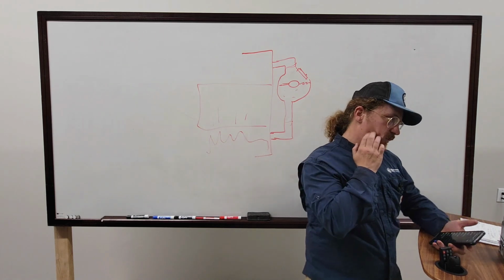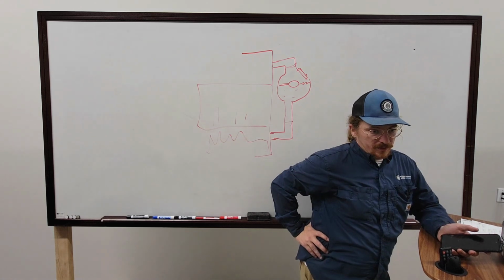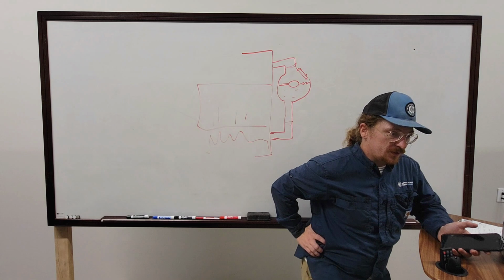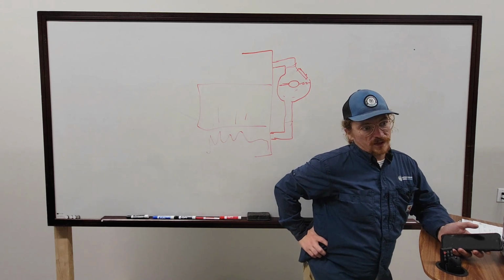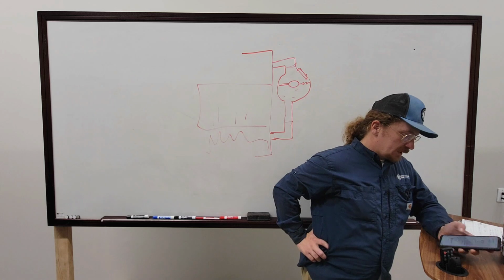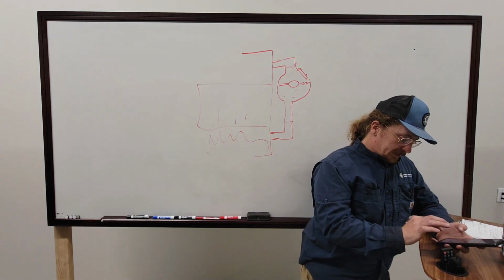Touch on flue gas analysis? No. You want stack temperature below 400, excess oxygen 8, and CO below 100, or 200? Parts per million? Okay, let me pull one up here.